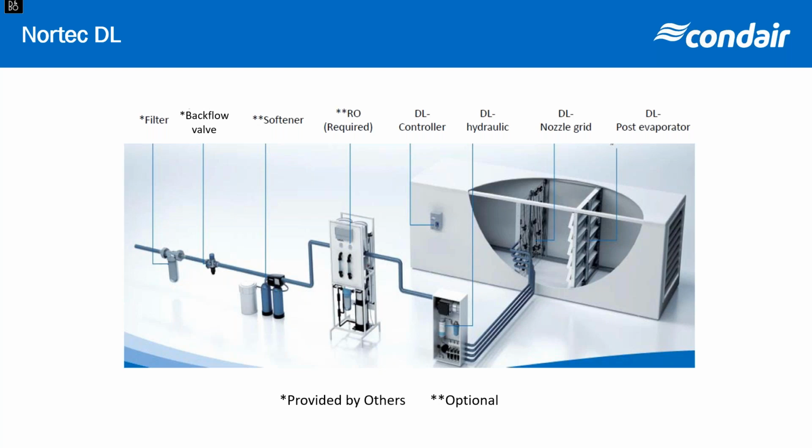It's in duct. It takes up very little space, but it overcomes some of the issues that people have with humidifiers. And let's be honest, our humidifiers are known as being expensive to operate, and they are dirty and require a lot of maintenance if you're using potable water with scale. So this system was developed specifically for clean applications, healthcare, biosciences, long-term care homes, etc. And it can be very low operating cost and very efficient.